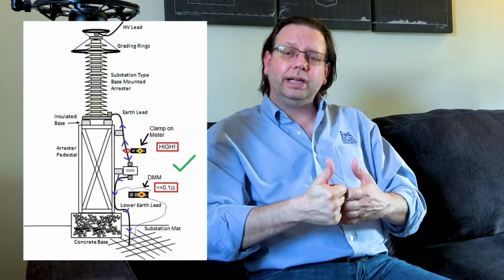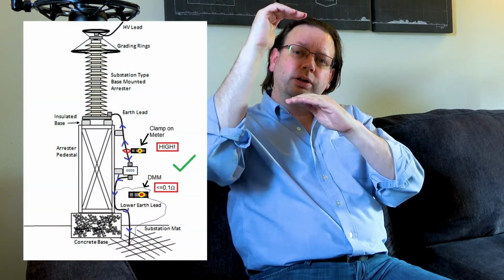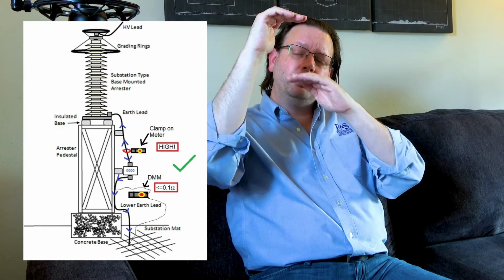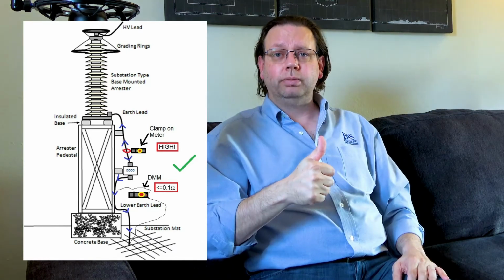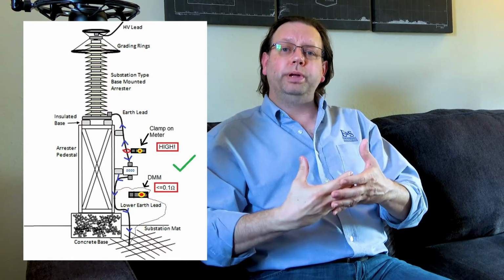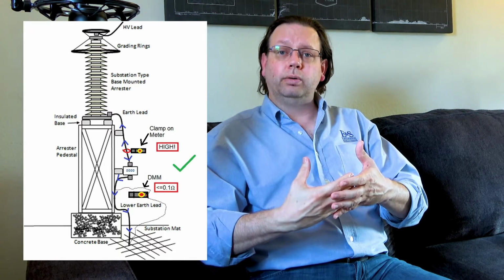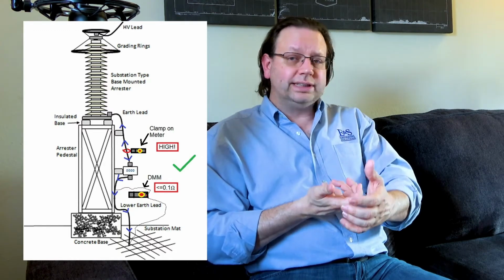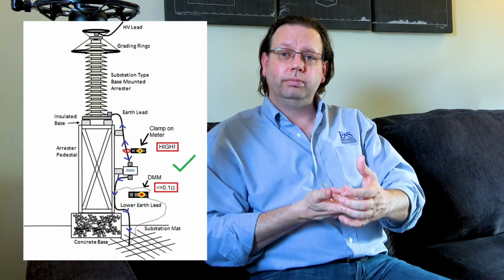When we walk up to that and we clamp on it now, our active Rogowski coil is trying to send energy in both directions. So it's going to send it down into the ground grid, but it's also going to send it up our lightning arrestor post. And because there's only one connection and there's an insulator between the wire and the post, it's going to go up and it's going to stop. And it's going to measure an open on our lightning arrestor. Our meter's going to say this has only a single connection, it's an open.